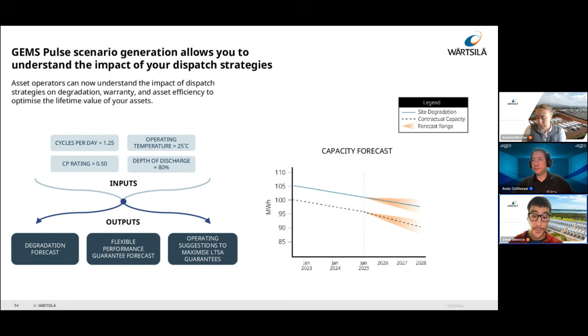One other interesting example: we found that for a specific site, operating at 100% depth of discharge and 1 cycle per day was equivalent to operating at 1.3 cycles per day and 80% depth of discharge—the degradation rate would be essentially the same. So it's interesting that there are multiple points of similar degradation based on different operating strategies.